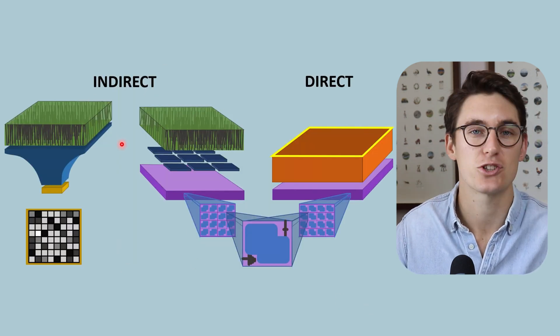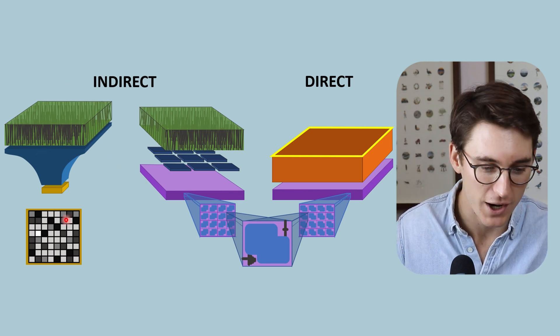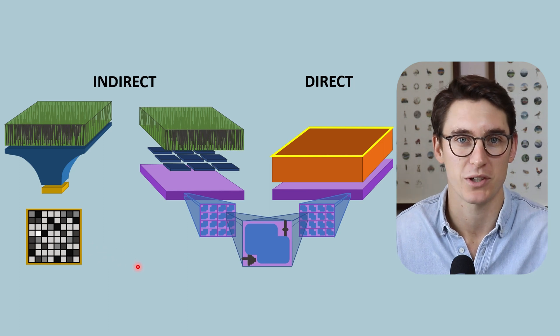Now our CCD system falls under the indirect digital radiography systems because X-rays are required to be converted into light prior to an electronic image being created.